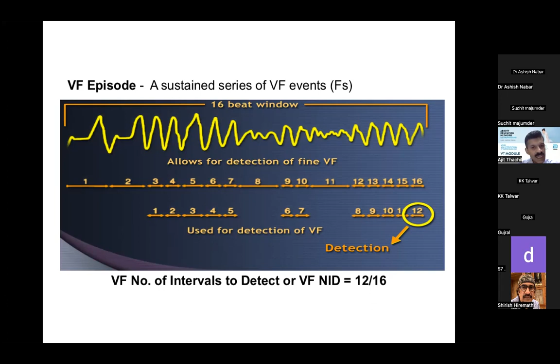But there we have this safety margin. That is, if 12 out of 16 RR intervals fall in the VF zone, it is called a ventricular fibrillation. So that's called the probabilistic count. All ventricular fibrillation will be in a probabilistic count in all manufacturers. So that's the 12 out of 16 or the 24 out of 36 or the 30 out of 80. Whereas the other one where you see only a single number, it's a consecutive count.